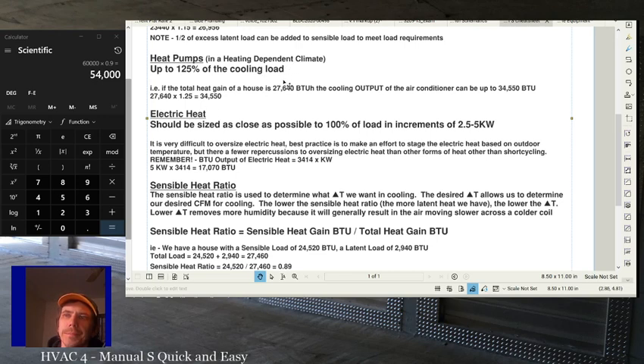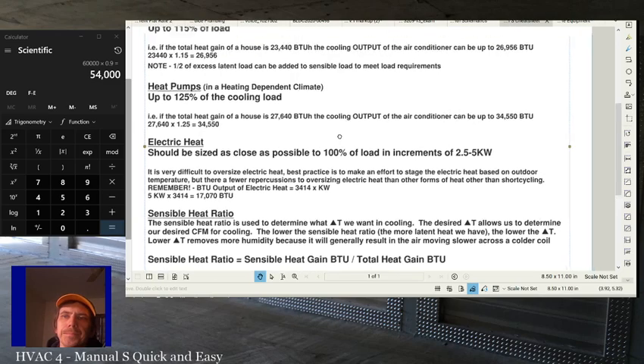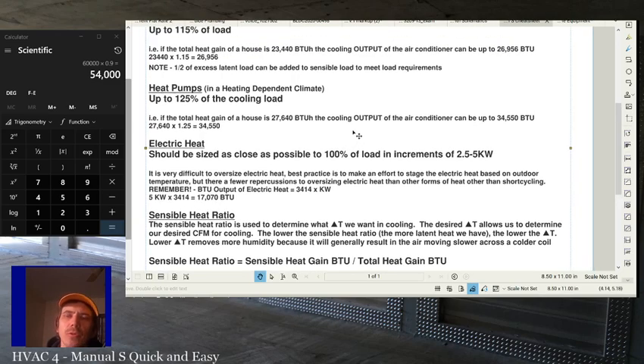And the dangers of oversizing are slightly overstated here and there. It's going to be hard for you really to get to the point where you're short cycling so bad you don't get any latent heat removal, especially if you set fan speed to deal with latent heat more if you need to. In general, I know we say 400 CFM per ton, but really you want to shoot closer to 350 to 375 CFM per ton for our area anyway. Most equipment these days kind of gets set up for closer to 350 CFM out of the box.